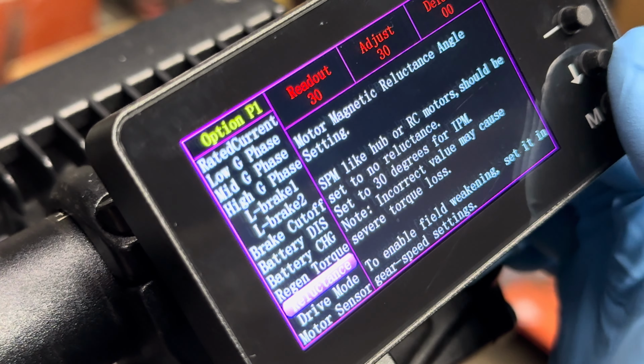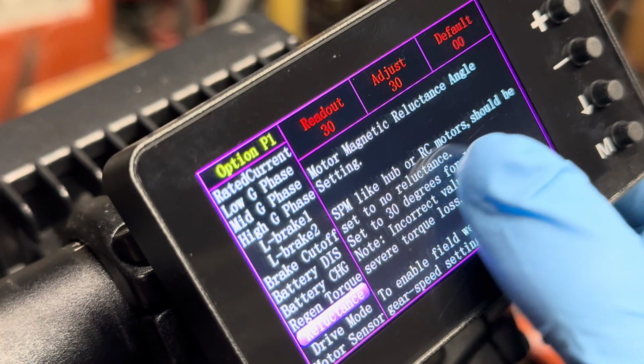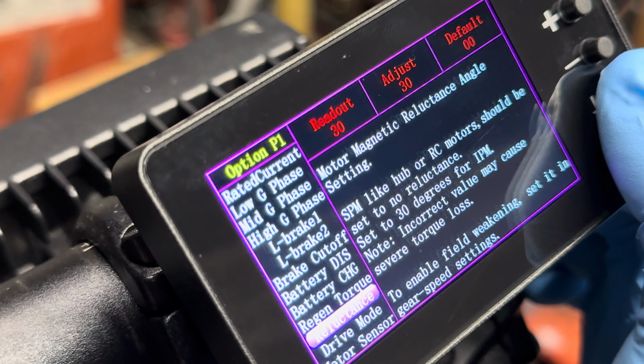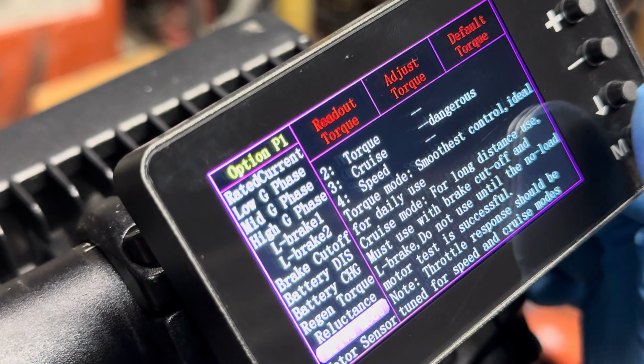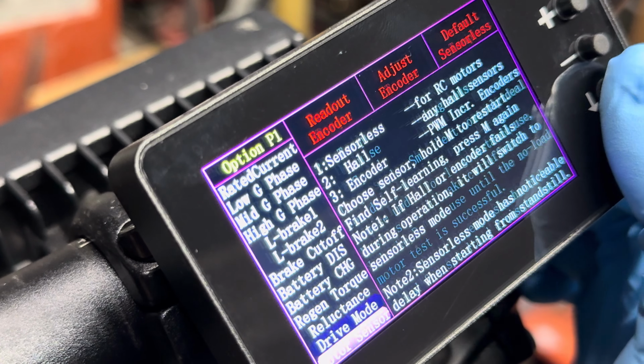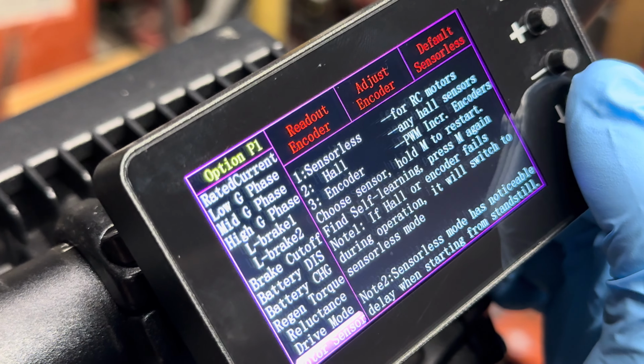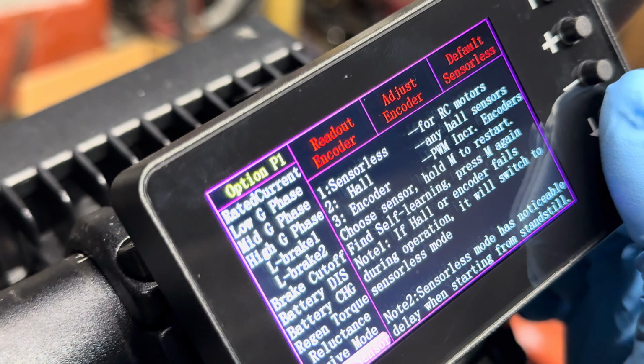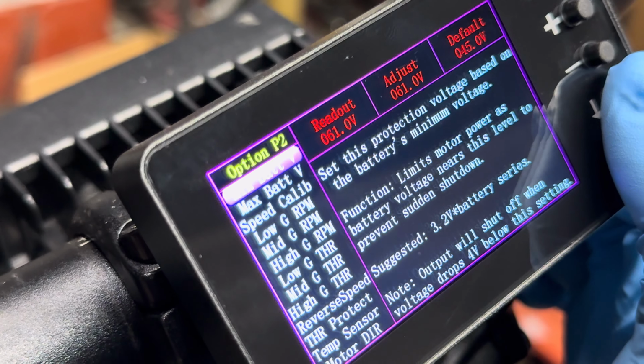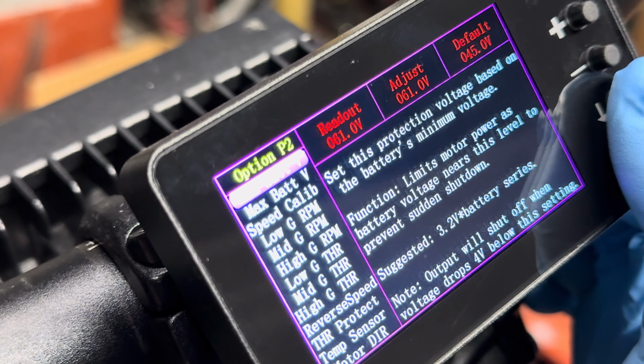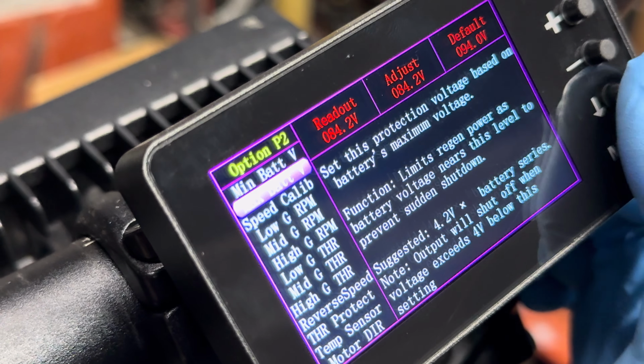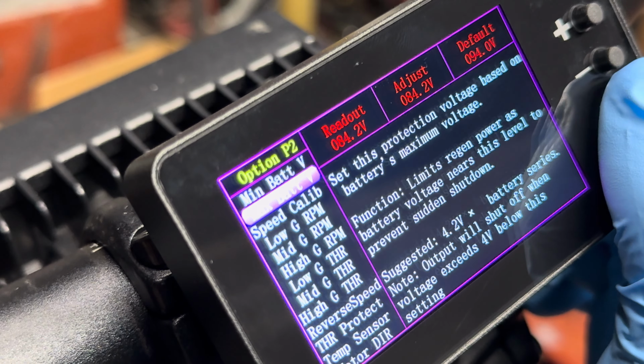Reluctance, this is an IPM motor, so we need to set that to 30, just like it states in the description. Drive mode, torque, that's going to be what you're used to the most. The E-Ride Pros use an encoder, so we have this motor sensor set to encoder. Minimum battery voltage, it's a 72 volt battery. We have it set to 61 volts. Max battery voltage, we have set to 84.2 because it is a 72 volt.